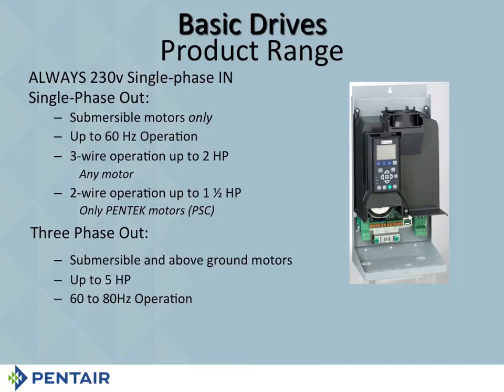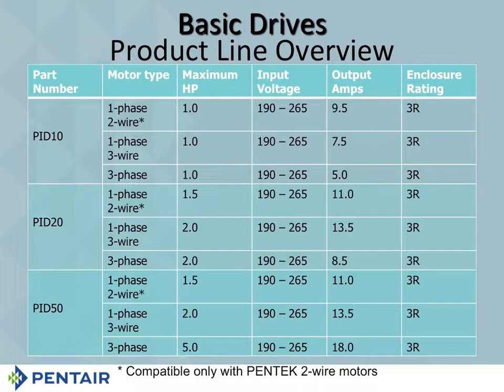Now, again, if you're going to do 80 hertz, it has to be submersibles only. You cannot do 80 hertz with above ground motors. They can't handle it the same way submersible motors can. As I said, there are some differences there. We're always going to recommend 60 hertz. Now, I'm really excited to show you this because you've really only got 3 different drives. And if you wanted to, you only needed to buy the PID 50. It will run everything.